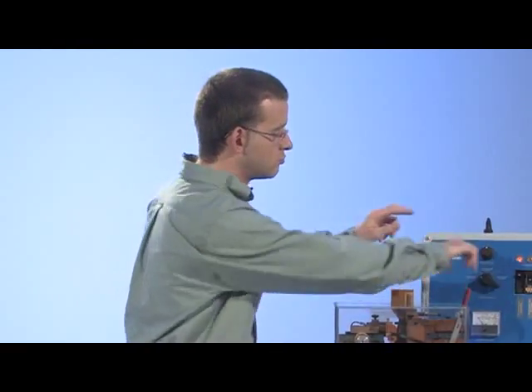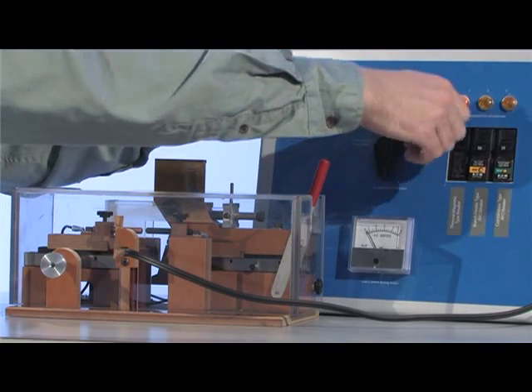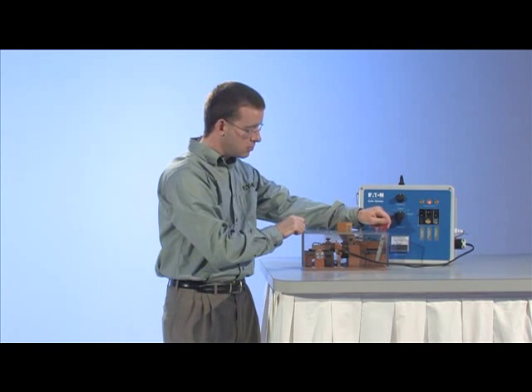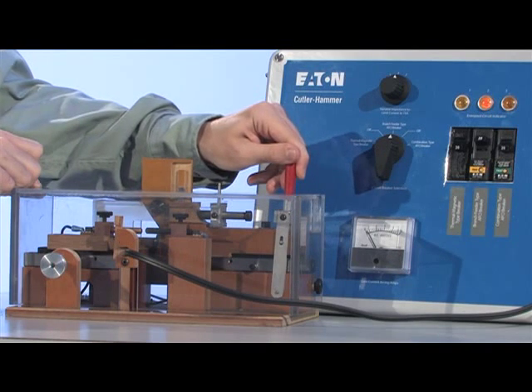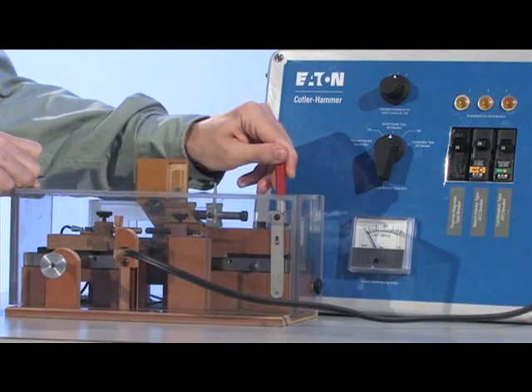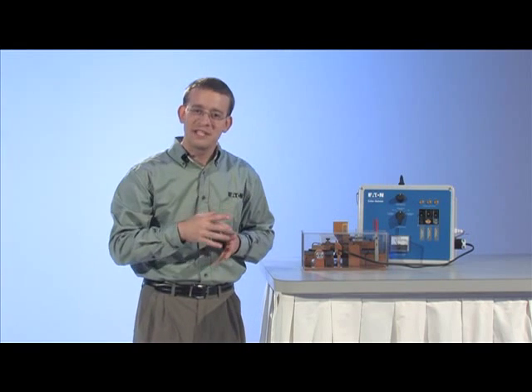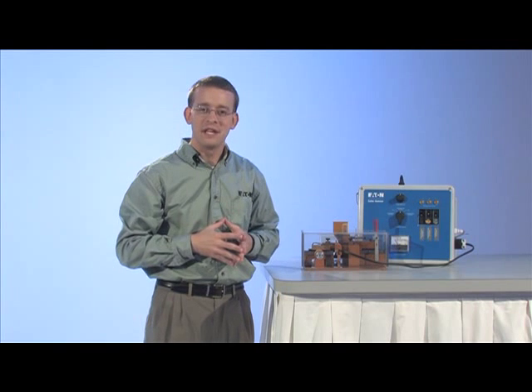So let's try the same test with an AFCI breaker. As we see, the branch feeder AFCI trips under this circumstance. While this AFCI breaker has been providing fire protection for many years, additional studies have found that another type of arcing also contributes to electrical fires.